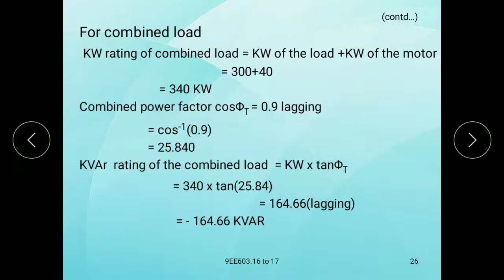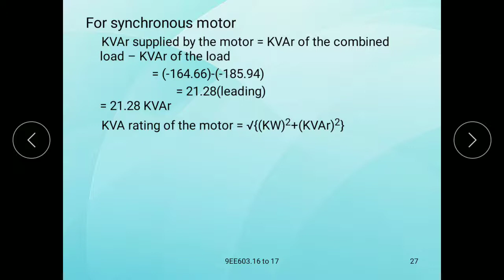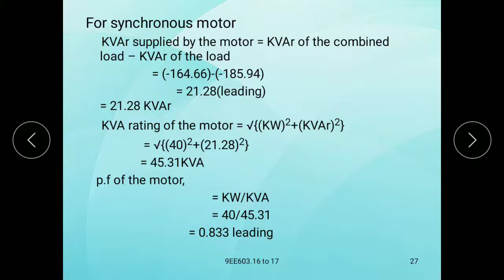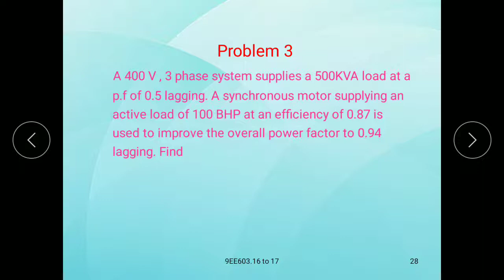Here for the synchronous motor, the KVAR supplied by the motor is equal to the KVAR of the combined load minus the KVAR of the load, that is minus 164.66 minus of minus 185.94, equal to 21.28 leading KVAR. Now the KVA rating of the motor is the square root of KW squared plus KVAR squared, that is 45.31 KVA. The power factor of the motor is KW by KVA, the value is 0.883 leading. Now problem 3; we will see problem 3 after that.